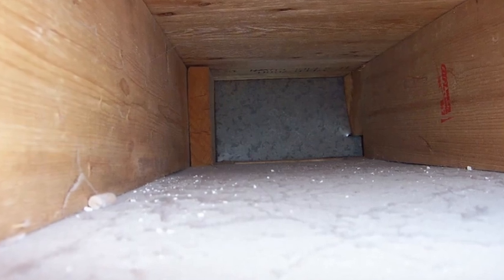First, some background. In pretty much all homes, the supply side that delivers conditioned air is hard ducted, meaning there is actual ductwork running from the equipment all the way to the supply register or diffuser. It's been a code requirement since forever to contain that conditioned supply air in actual duct materials, like sheet metal, flex duct, or ductboard. In the past, in some markets, the return sides were also almost always hard ducted as well. However, until recently, most codes allowed the builders to instead use the hollow wall and floor cavities to return the ambient temperature house air back to the equipment for either some or practically all of the return system.